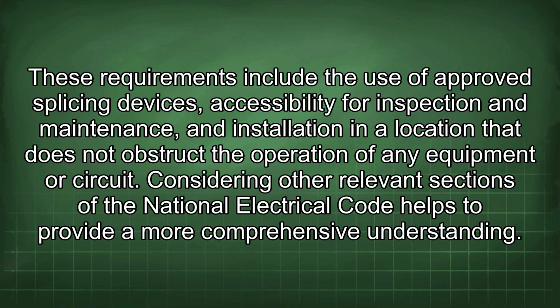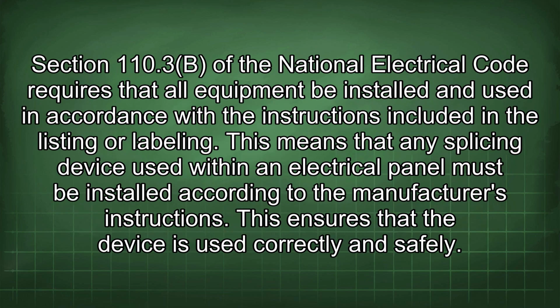Considering other relevant sections of the National Electrical Code helps to provide a more comprehensive understanding. Section 110.3(b) of the National Electrical Code requires that all equipment be installed and used in accordance with the instructions included in the listing or labeling. This means that any splicing device used within an electrical panel must be installed according to the manufacturer's instructions. This ensures that the device is used correctly and safely.